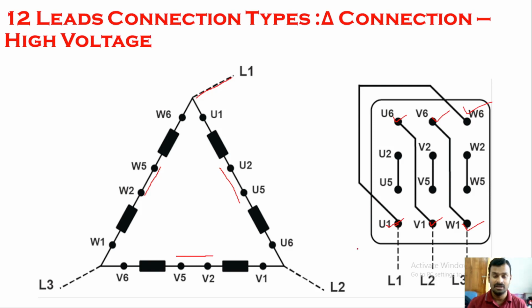For the 12 lead connection type for delta connection, you can also see here L1 connected to U1 and W6, L2 connected to U6 and V1, L3 connected to W1 and V6. And the remaining ones, W2 W5 will be shorted, U2 U5 will be shorted, V2 V5 will be shorted. If you connect in this configuration, it will act as a high voltage delta configuration. So these are the different possible configurations for these motors, either a 9 terminal dual voltage motor or a 12 terminal dual voltage motor.